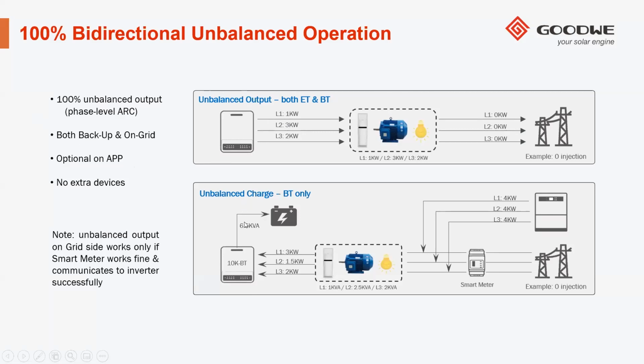Our BT inverter, which is the AC retrofit without MPPTs, can have unbalanced charging as well. What that does is it tries to equalize the load from the grid. This is especially important for net metering and time of use tariffs to ensure that the peak demand is reduced. So it will then evenly draw from the grid to ensure that each phase is equal.